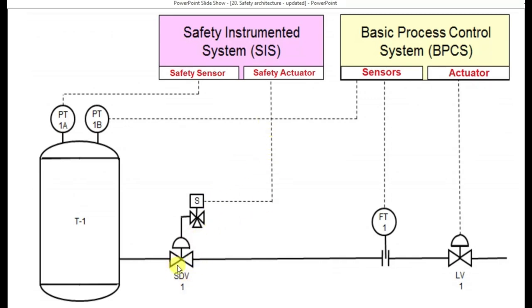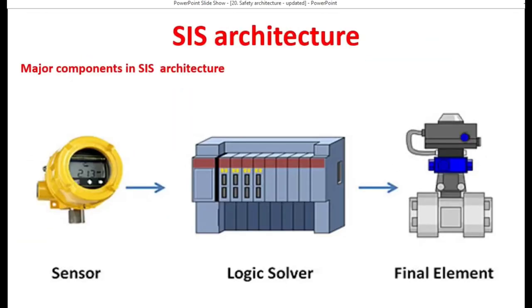The safety instrumented system — with the logic built inside the logic solver — will do the necessary action and give the command to close the shutdown valve, so that liquid entry into the reactor will get minimized or controlled. The pressure transmitter, safety instrumented system logic solver, and valve are all acting independently. That is why it is known as an independent protection layer.